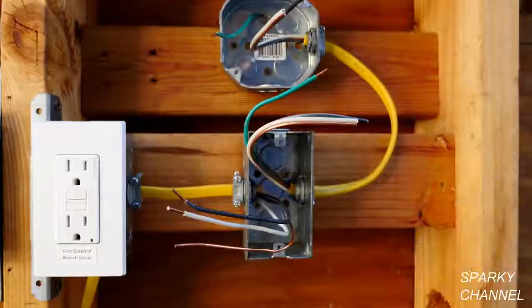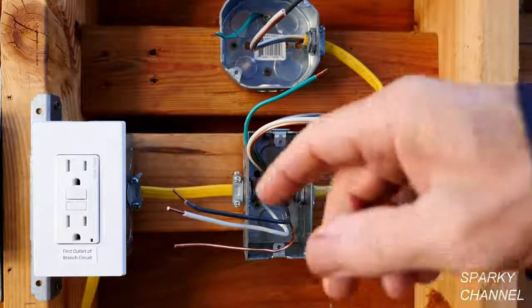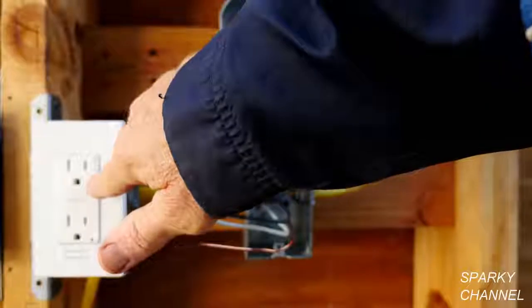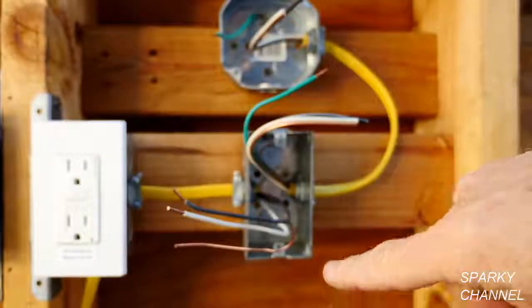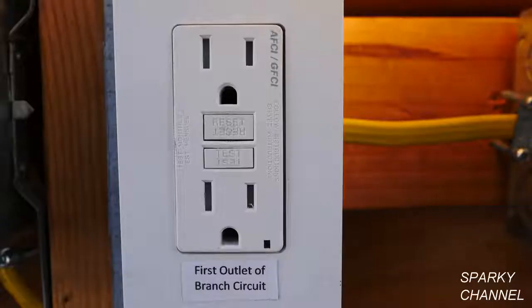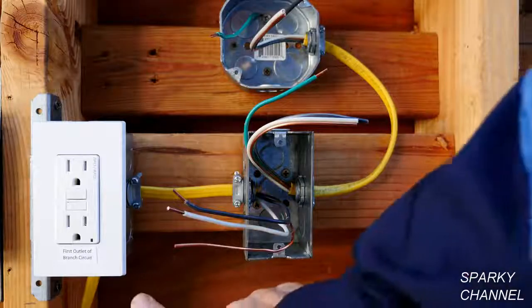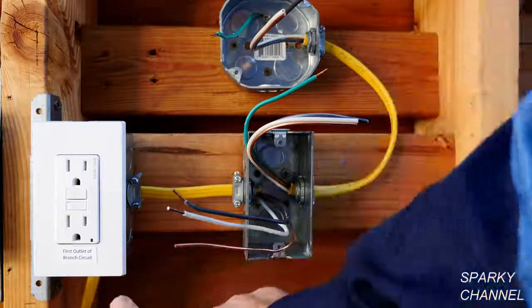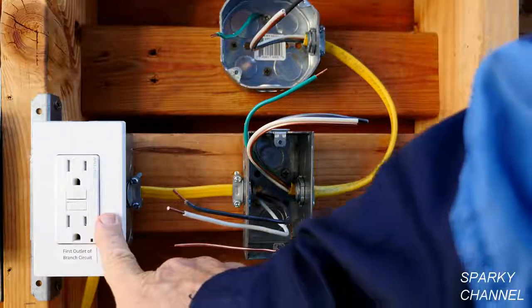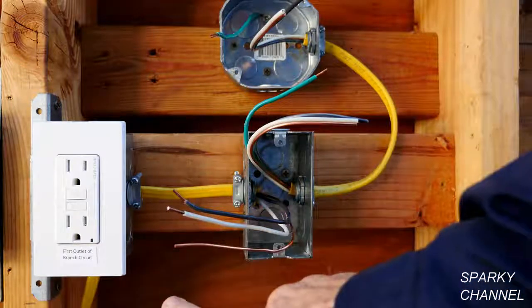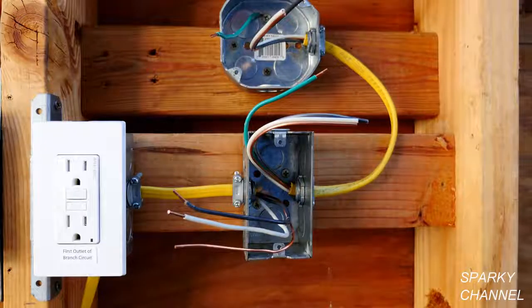Some of the highlights that you might want to know is that these receptacles must always be put on the first box in the circuit. They have to be labeled first outlet of branch circuit. The receptacle is labeled AFCI GFCI, so that's taken care of. Another thing that you need to know is that this cable that feeds this first box of the circuit must be unbroken from the main panel. That's all covered in 210.12 in your code book, and it's in my video as well that I'll put a link for in my video description.